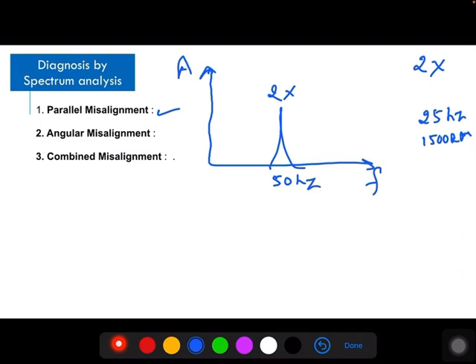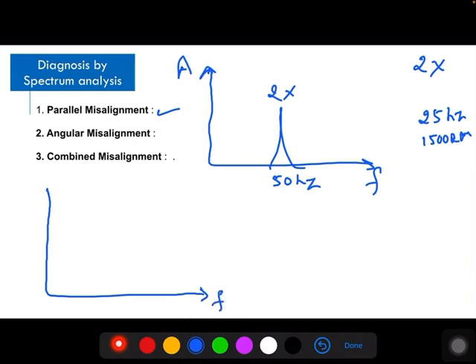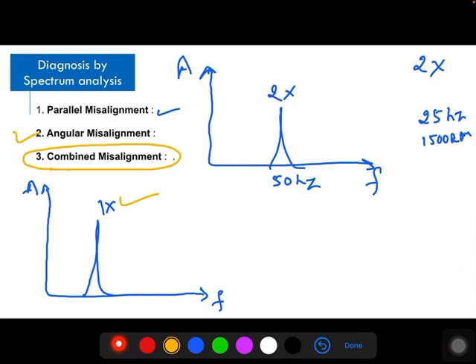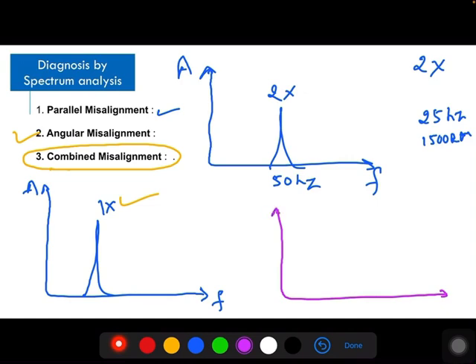In the case of angular misalignment, for each rotation of the shaft it produces one peak — one vibration pulse per revolution. Then in the spectrum, you are getting 1x RPM. But equipment always has a combination of both parallel and angular misalignment — this is called combined misalignment. There will not be purely parallel or purely angular; there will always be a combination of both. Then for combined misalignment, you will get both 1x and 2x in the spectrum.